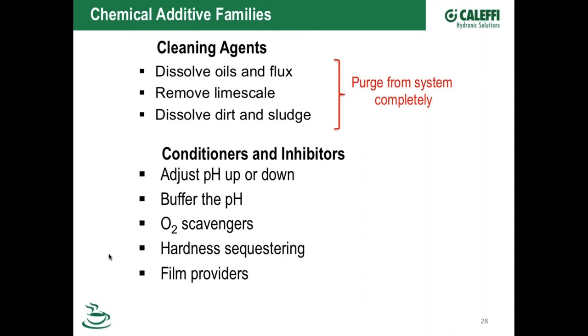I think the most important reason to use some of these inhibitor chemicals is they have a film provider. So once you've stripped your metal down to bare copper and bare stainless steel with your cleaners, your soaps or your acids, what the film providers do is get in there and put a micron thick layer of film. It's almost like when you anodize aluminum - really what you're doing is rusting or corroding the aluminum to give it a protective layer so it doesn't attack the metal below it, like lawn furniture or outboard motors that are typically anodized aluminum. Just putting a film over the top layer protects it.